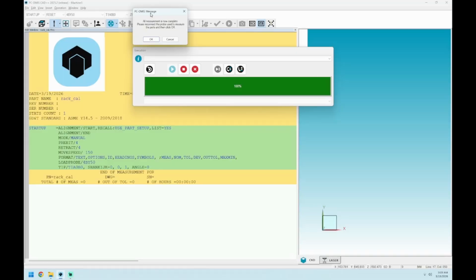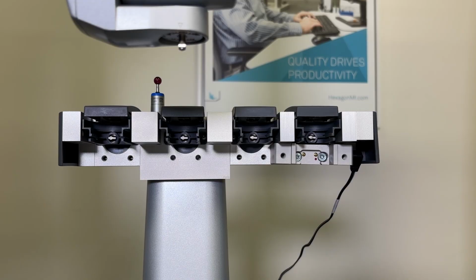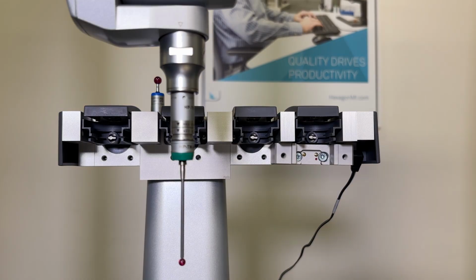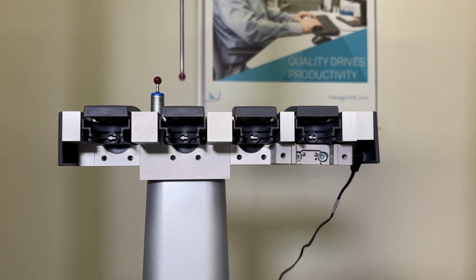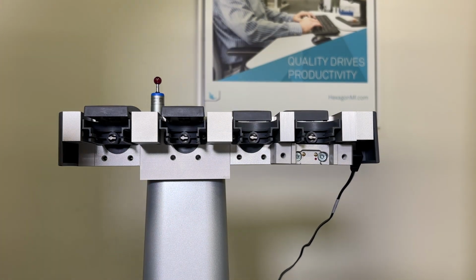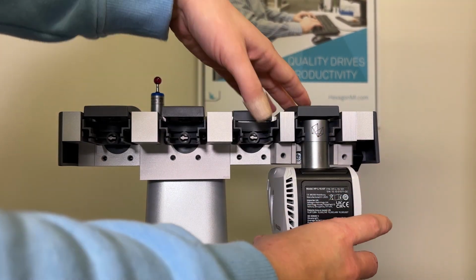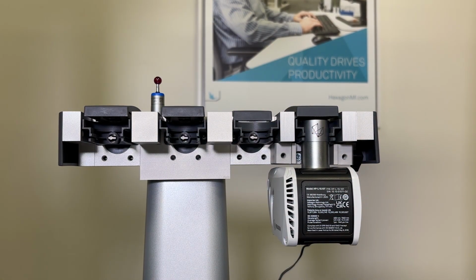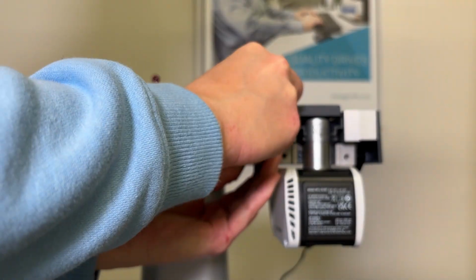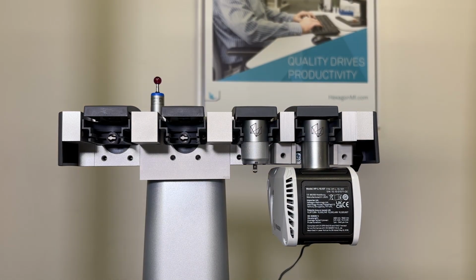PC-DMIS then tells you that all measurements are complete and that you are free to reconnect the probe used to measure the ports, and then you will click OK. Please make sure you do not over-tighten the key when you are reattaching the probe. It should be completely horizontal when you are done tightening it. If you over-tighten it, you run the risk of damaging the components. I'm also putting all of the attachments back on the rack and making sure all of the lids are closed.